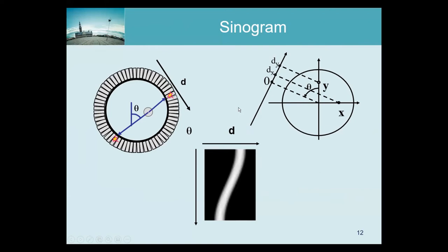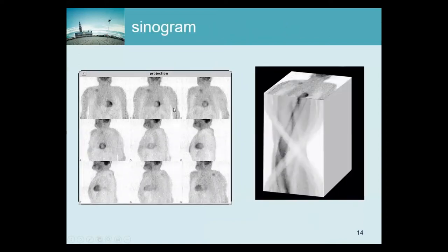This is for a PET. So for PET, if we take these views and we take a single row in every view—these are just nine but we have many of them—and if you put them one below the other, we get this. So here a PET sinogram, only over 180 degrees because we measure the whole line at once. 360 degrees doesn't mean too much, but we could easily synthesize a 360-degree sinogram from it, because this line should be the same as that line except that it's mirrored. So we can mirror the whole sinogram and glue it below here, and then it will produce a nice 360.